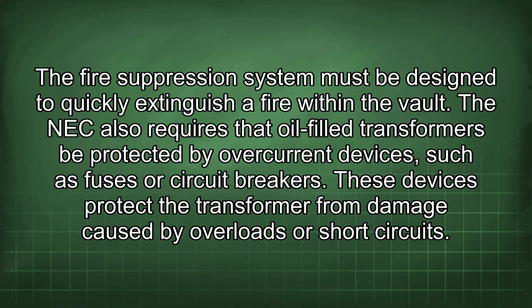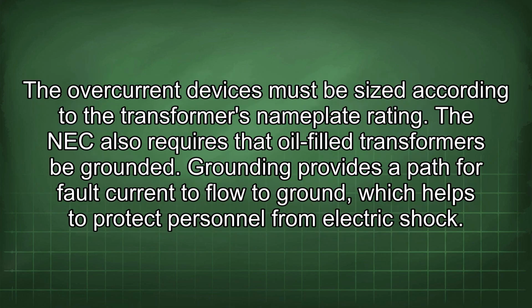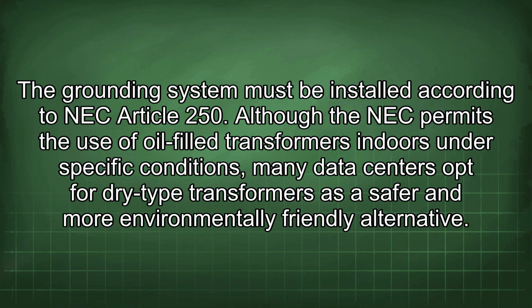The NEC also requires that oil-filled transformers be protected by overcurrent devices, such as fuses or circuit breakers. These devices protect the transformer from damage caused by overloads or short circuits. The overcurrent devices must be sized according to the transformer's nameplate rating. The NEC also requires that oil-filled transformers be grounded. Grounding provides a path for fault current to flow to ground, which helps to protect personnel from electric shock. The grounding system must be installed according to NEC Article 250.